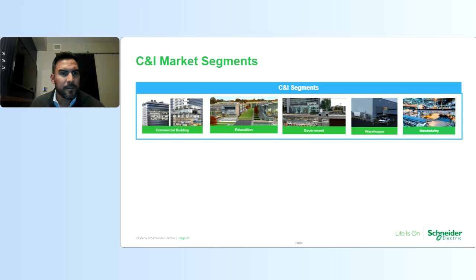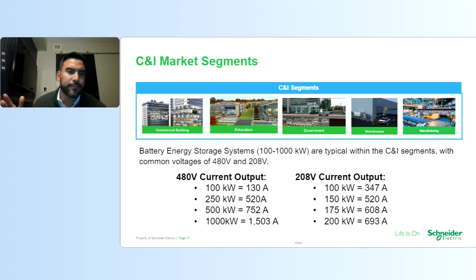So we'll talk about the C&I market segments. C&I can refer to commercial, buildings, education, government facilities, warehouses, manufacturing. It's essentially where a lot of the manufacturing and emergence of these on-site microgrids are becoming more prevalent. And as we're seeing, the common energy storage systems for commercial application are between about 100 to 1,000 kW. And that's typical within this C&I segment. And most of the common voltages here are 480 and 208 volt. And I highlight here the current output rating of these energy storage systems. So if you're dealing with a 480 volt system, 100 kW, you're getting about 130 amps. And really the most common sizes go all the way up to 1 megawatt or 1,000 kilowatts, where you get about 1,500 to 1,600 amps of full load amps to your system. Now, why is that important?